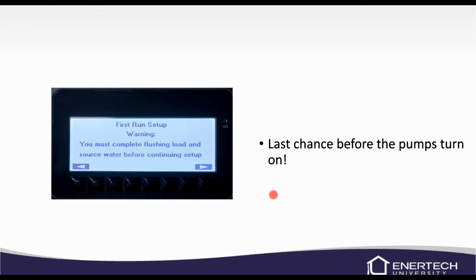After you've done that, it's going to give you a warning that you must complete the flushing before we continue to the next step, because we're going to turn the pumps on and check our water flow. If you haven't flushed, obviously that's going to affect your water flow if you've got air in there. So make sure you've got it flushed, and then we can go ahead and move on.